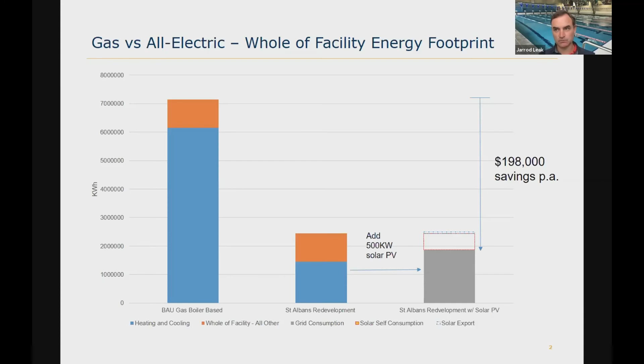This has already been alluded to, but before setting out to do all-electric heating and cooling systems, you're not going to get anywhere if you don't start with a high performance building envelope. This project had R and U values for the walls and windows specified well above minimum code requirements, which are woeful anyway, but we went well above. We've got airtightness testing occurring during construction to ensure the integrity of the process, and we're getting what we paid for. We've also got heat recovery systems and an optimized pool hall air handling unit applied to both the pool hall and the pool backwash water tank, recovering heat from there and reincorporating it into the cycle.